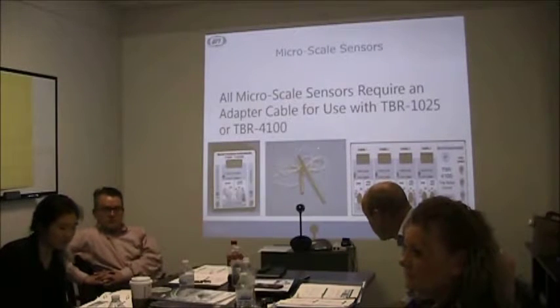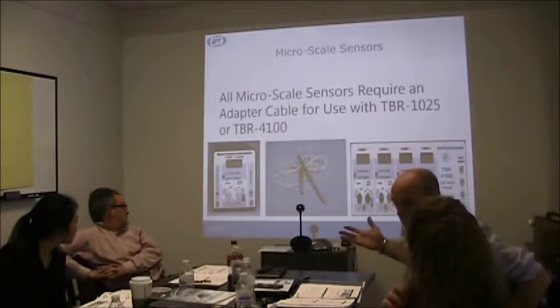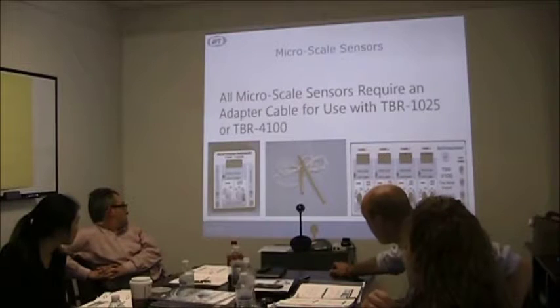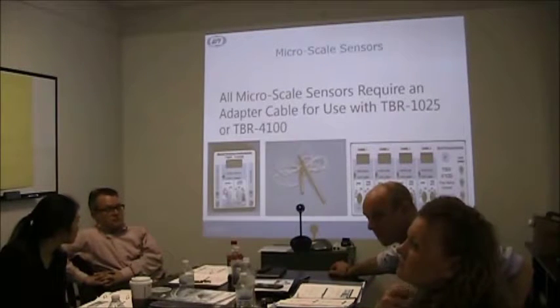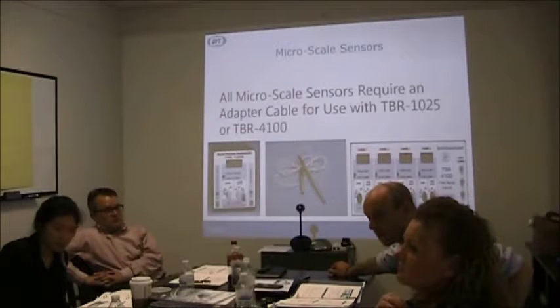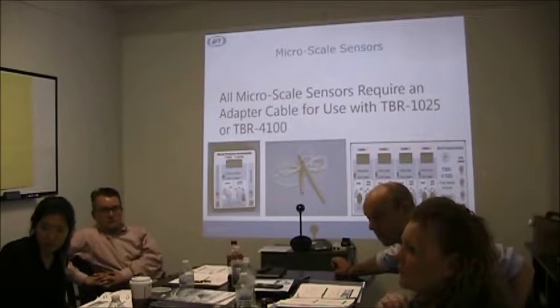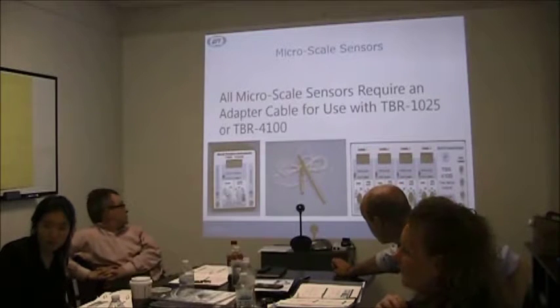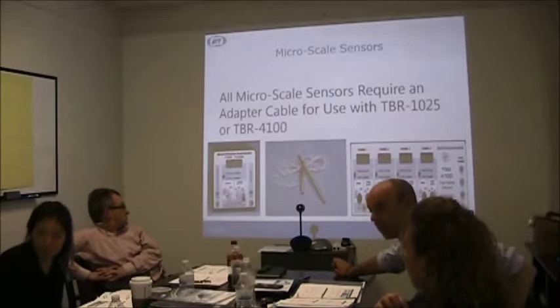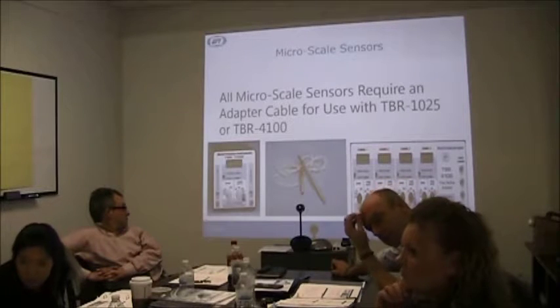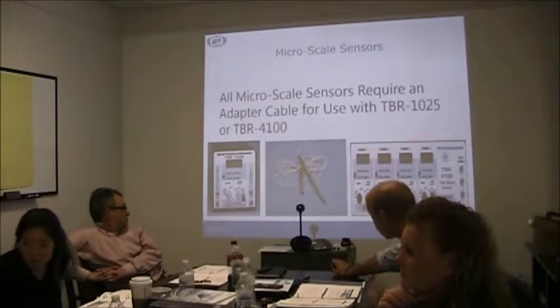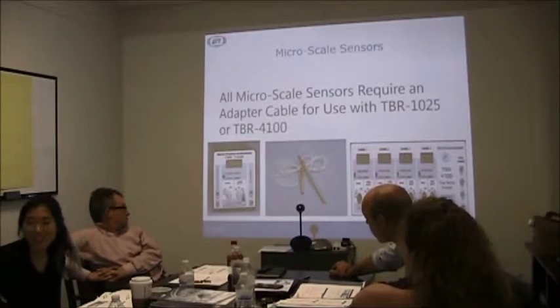And when are you changing the under range? Yeah, the range can be based, one, on the application, and two, on the type of sensor that we have. A lot of times, people are testing at 37C to mimic human blood conditions. Because of that, a lot of times people will be operating in this 100 nanoamp range. If they're measuring current, they can certainly measure in voltage or any other type of units they choose to.